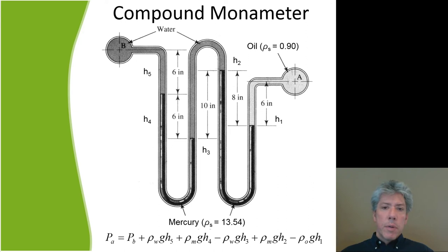Why would you ever need a compound manometer? Well, these manometers can be used, as I said, for relatively small pressure differences between two points. But a lot of times even then you need a manometer that's very tall. A compound manometer can be used instead so that the manometer simply doesn't have to span such a large distance, say a couple of stories or something. Instead it can hang on a wall and be much shorter in height. So these are practical devices, but to be fair, electronic devices are so common today, inexpensive and sensitive, that they largely replace compound manometers. Now I have used a manometer. There's a time I needed to measure flow rate in some ducting in my home. Why was I going to go out and spend the money and go through the effort to, you know, say a hundred dollars to measure pressure difference between two points in duct work.